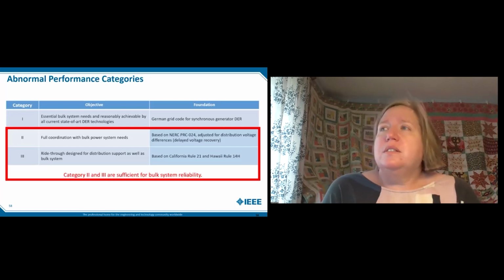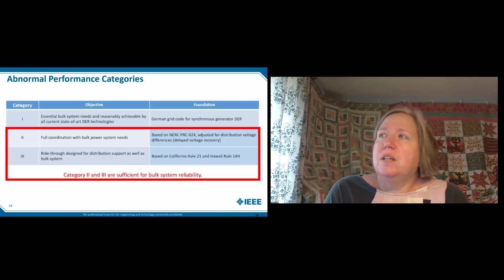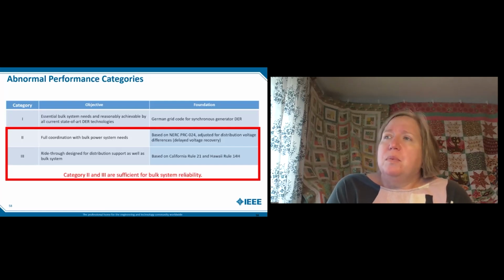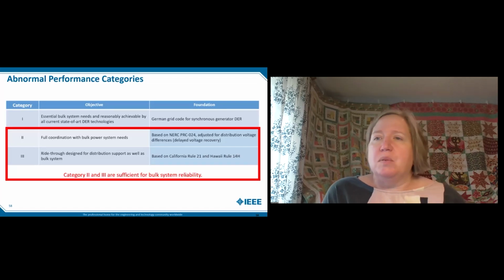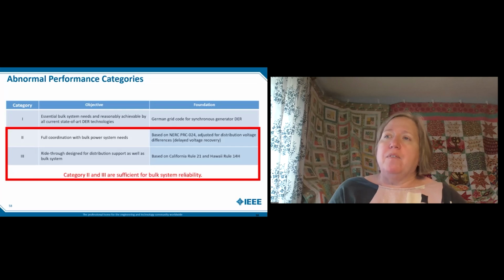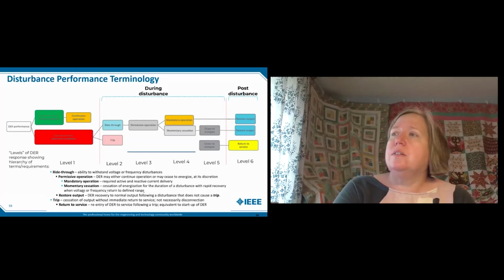Category 1 is the essential bulk system needs and is reasonably achievable by all DER technology. Category 2 is full coordination with bulk power systems. And category 3 is ride-through designed for distribution support as well as the bulk system. So category 2 is going to help you with the bulk system. Category 3 is going to help things on your distribution system along with your bulk system. We are in the revision. We are working on a category 4, which is for islanded systems, which I think will also be of great interest. Hawaii has had great input on that as they run islanded systems too. But those are the categories.